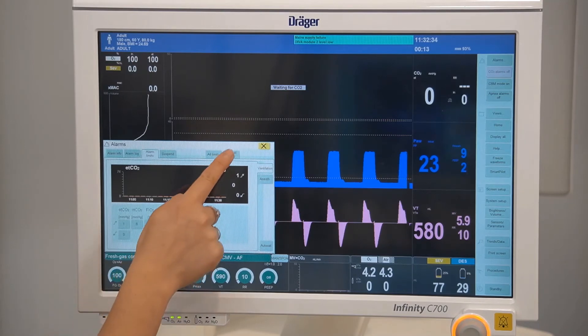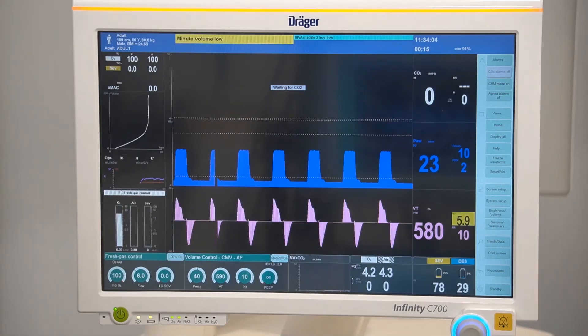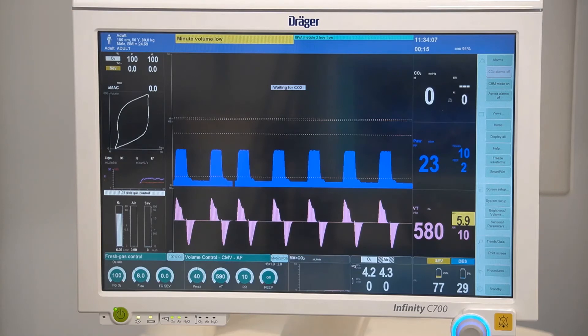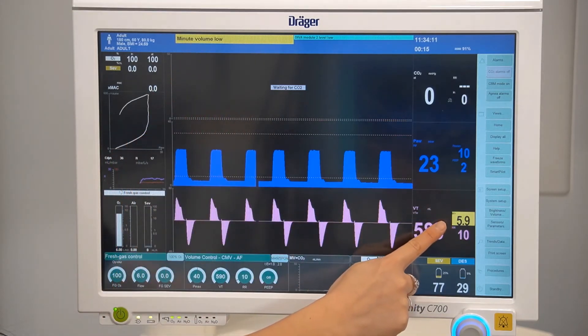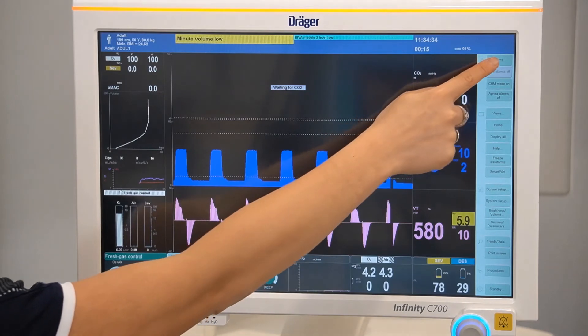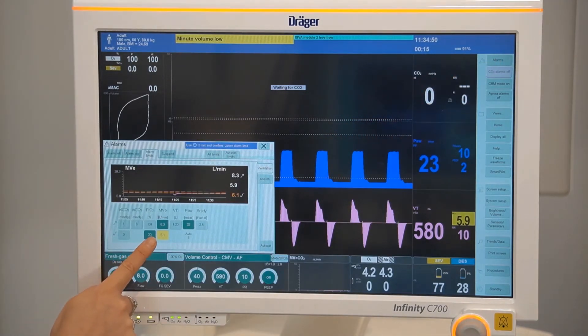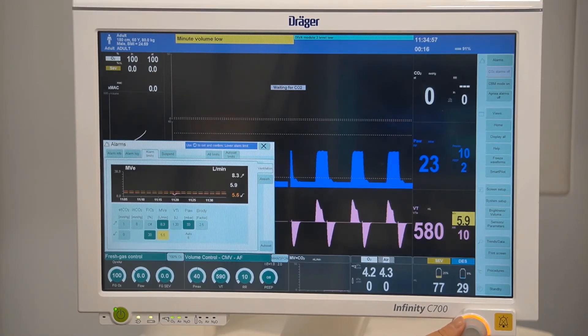Under auto set limits is where you can adjust your auto set values. In the event an alarm limit is breached, an alarm message will be displayed and the corresponding parameter box will flash. To adjust an alarm limit, select alarms from the main menu. Here you can see the breached alarm limit highlighted to allow for easy alarm management. Using the rotary knob, make your adjustment and then confirm.